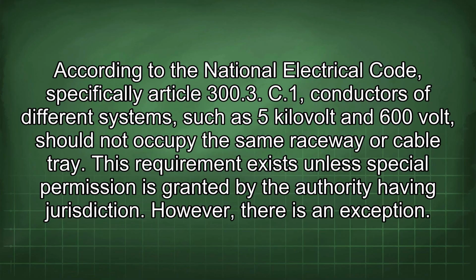According to the National Electrical Code, specifically Article 300.3(C)(1), conductors of different systems such as 5 kilovolt and 600 volt should not occupy the same raceway or cable tray. This requirement exists unless special permission is granted by the authority having jurisdiction. However, there is an exception.